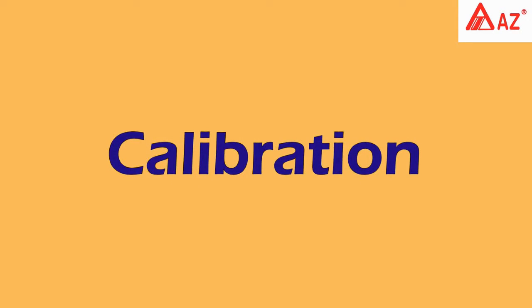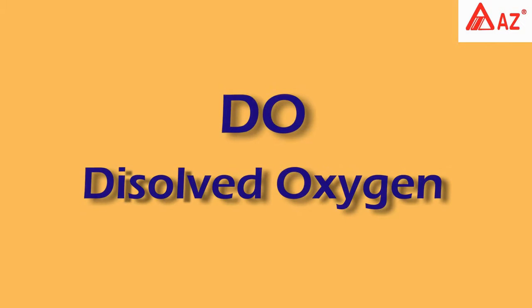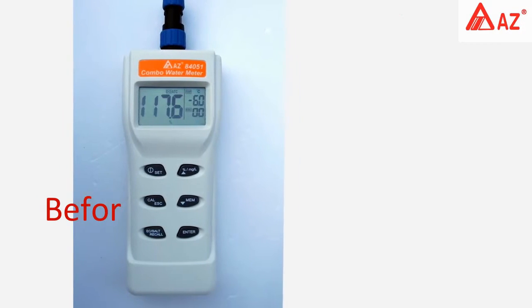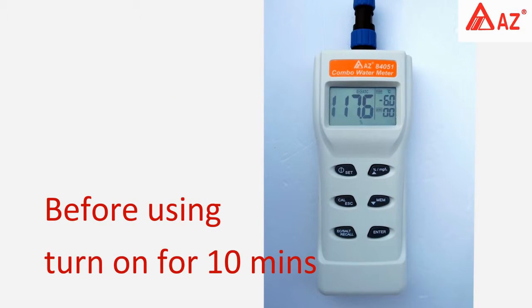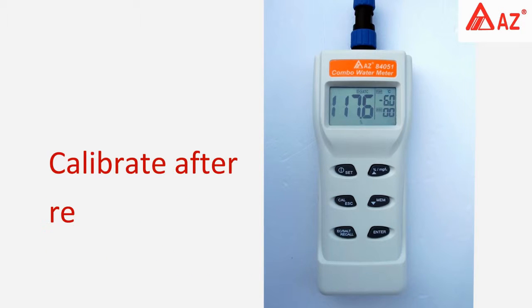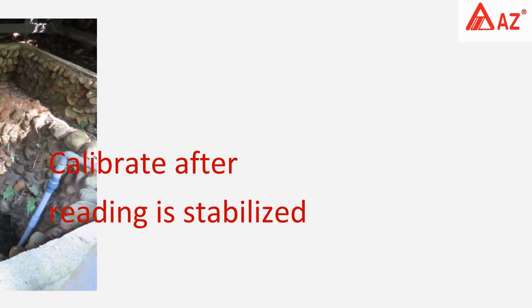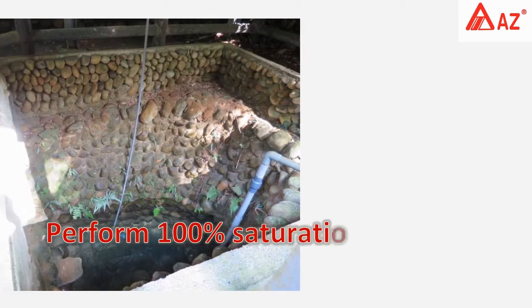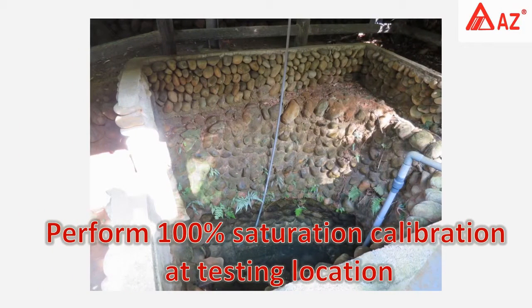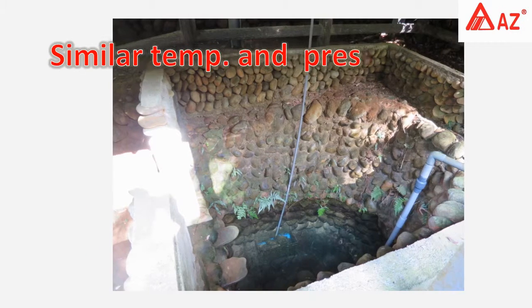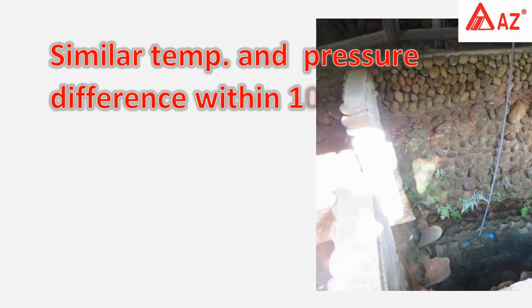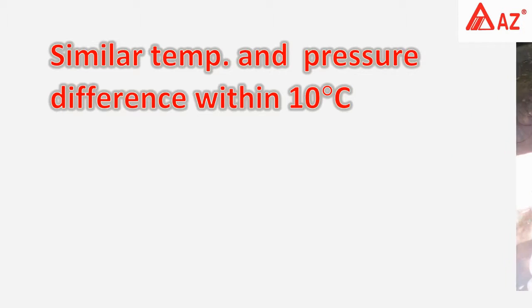Calibration. Dissolved oxygen: turn on the meter for 5 to 10 minutes, and calibrate after the reading is stabilized. Before each operation, you need to do a 100% saturation calibration at the testing location, or in a similar temperature and pressure environment. The temperature difference should be within 10 Celsius degrees.